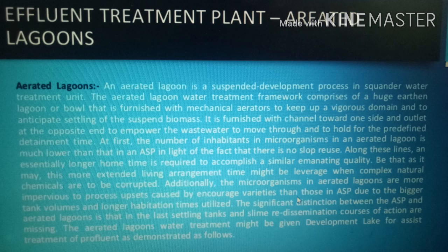Air is blown in the form of a stream of bubbles at the bottom with mechanical devices for about 2 to 6 days. During this time, a healthy flocculent sludge is formed which brings about oxidation of the dissolved organic matter, and biological oxygen demand removal in the range of 90% could be achieved.